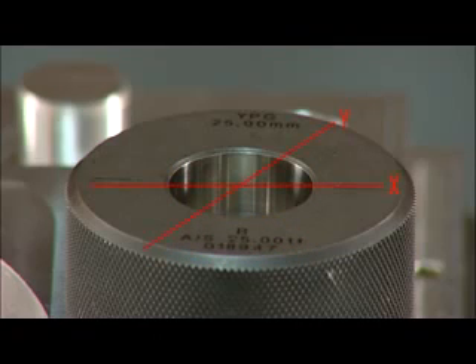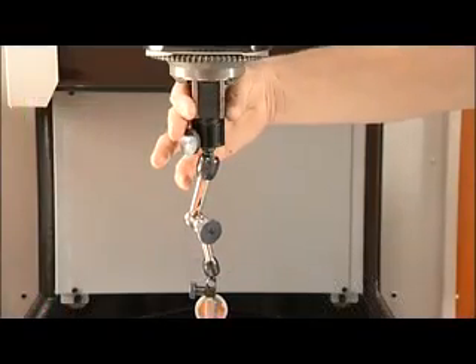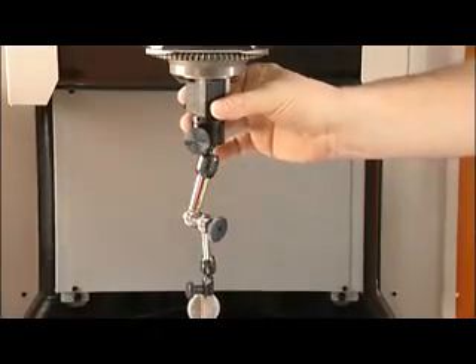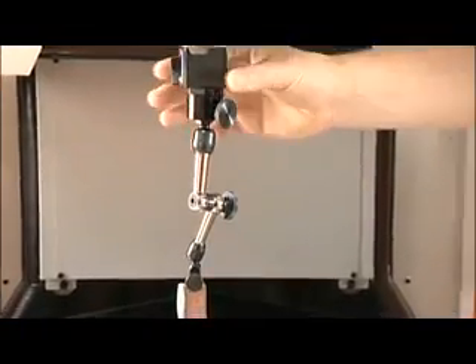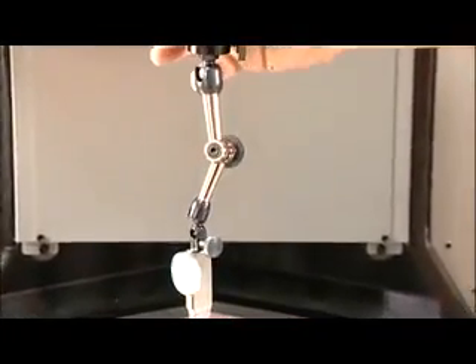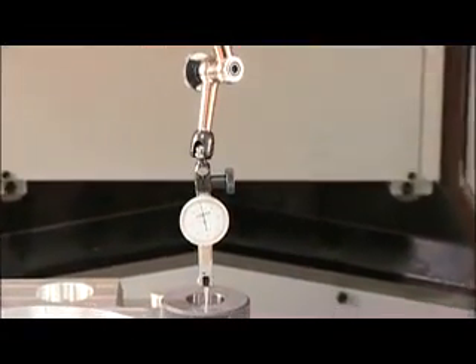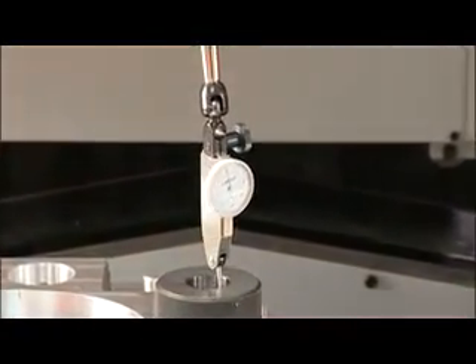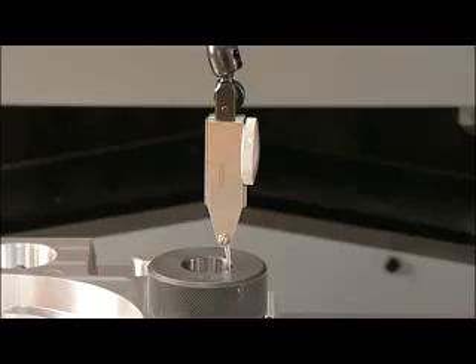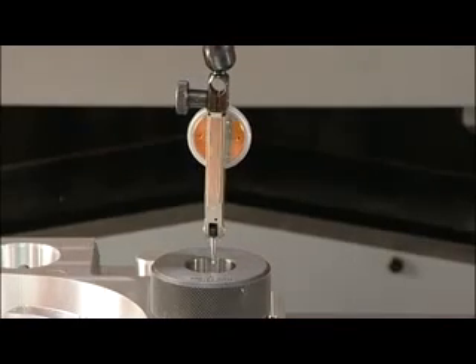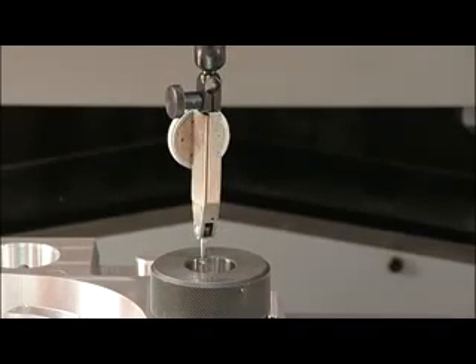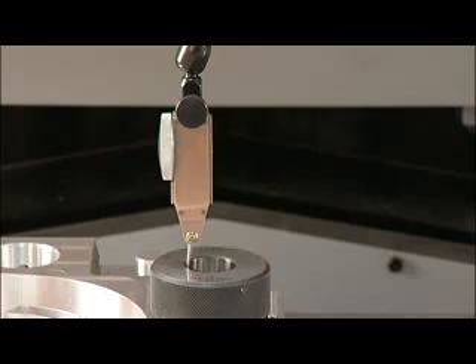Next, the X and Y position of the centre of the ring gauge must be determined. This can be found by setting the spindle roughly over the centre of the ring gauge, then mounting the dial test indicator on the spindle nose. Adjust the dial test indicator so that it remains in full contact with the ring gauge surface whilst being rotated by hand.